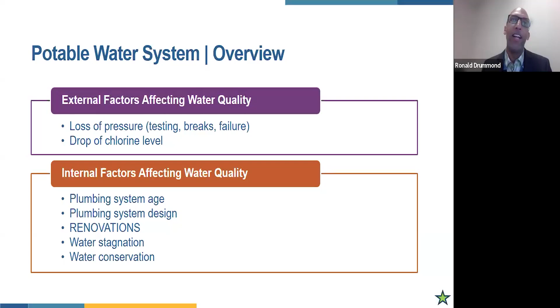One particular factor that is affecting water quality now is water conservation. Water conservation is great. We should all be striving for it. But in limiting the amount of water that's going through the system, we often don't change the pipe size of the plumbing systems that are used to convey that water. As a result, the velocities get slower, and that can lead to biofilm growth, and that does, as we talked about before, it might promote bacterial growth in the system.